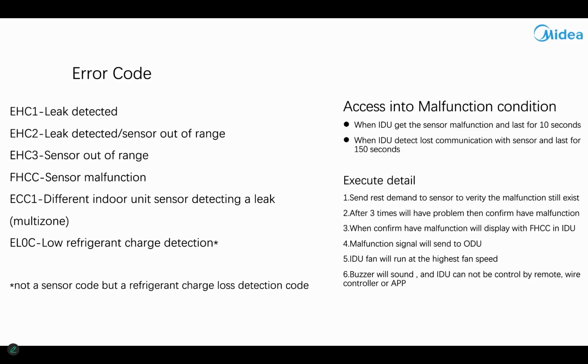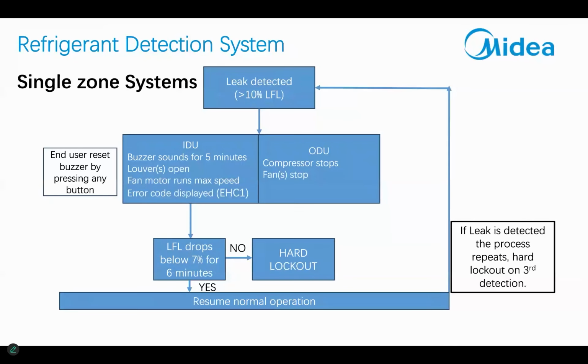That's pretty much the two you'll see: FHCC or EHC1. EHC1 is a leak detected. FHCC is a sensor malfunction or a loss of communication with the sensor. On leak detection, if it goes above 10% of the lower flammability limit, we go into mitigation. Compressor stops, fan stops. The buzzer sounds for 5 minutes. It can be reset by pressing any button, if the homeowner doesn't want to listen to it for 5 minutes. The fan motor comes on at max speed and the error EHC1 is displayed. It monitors this for 5 minutes.